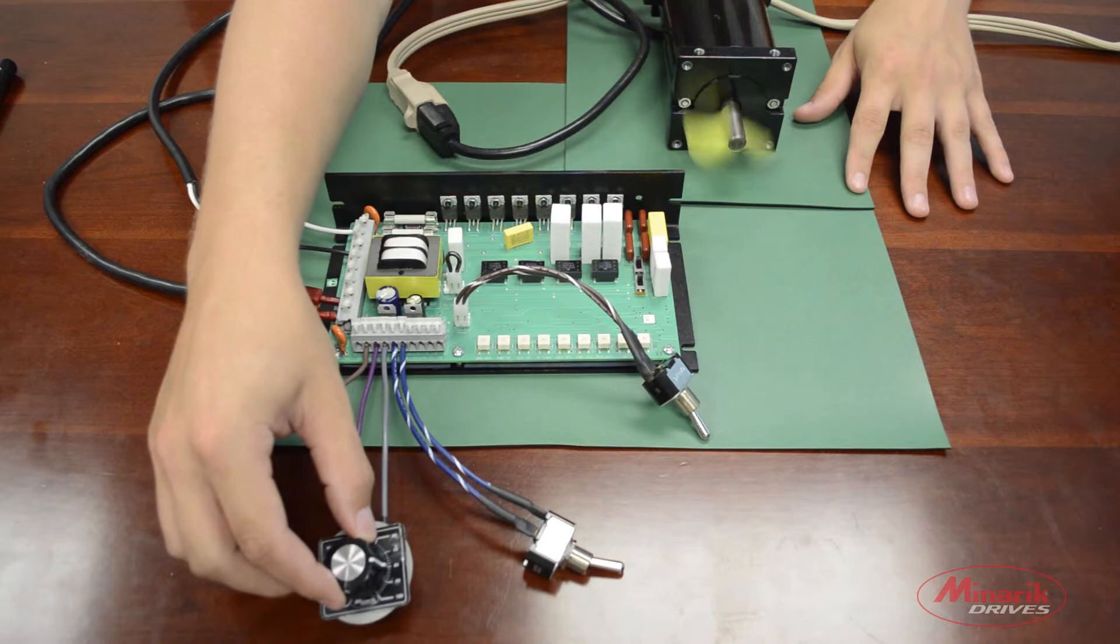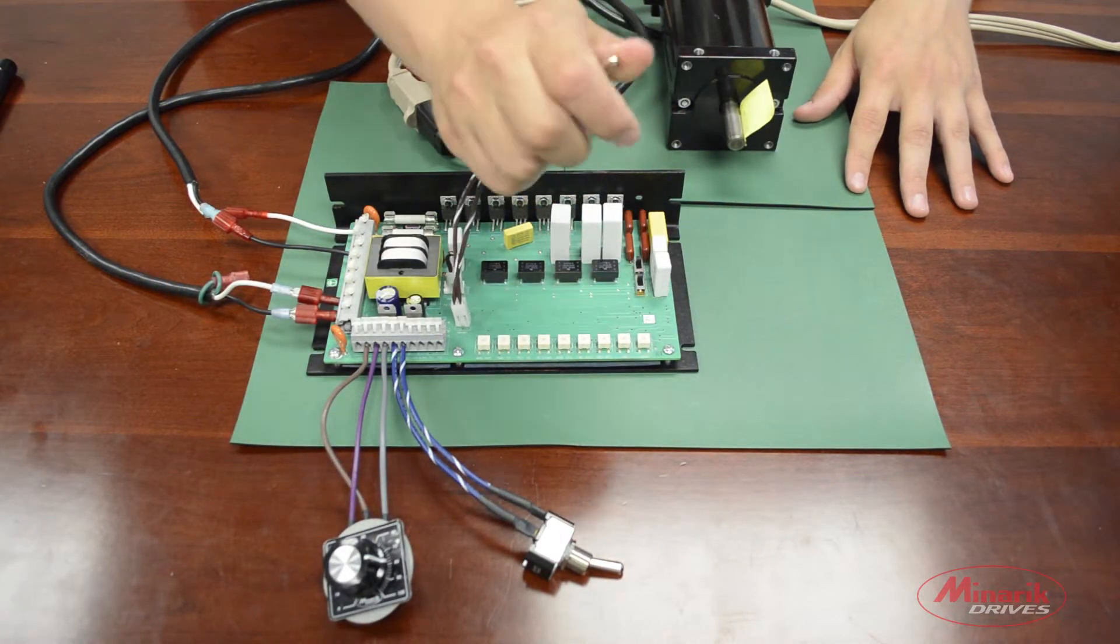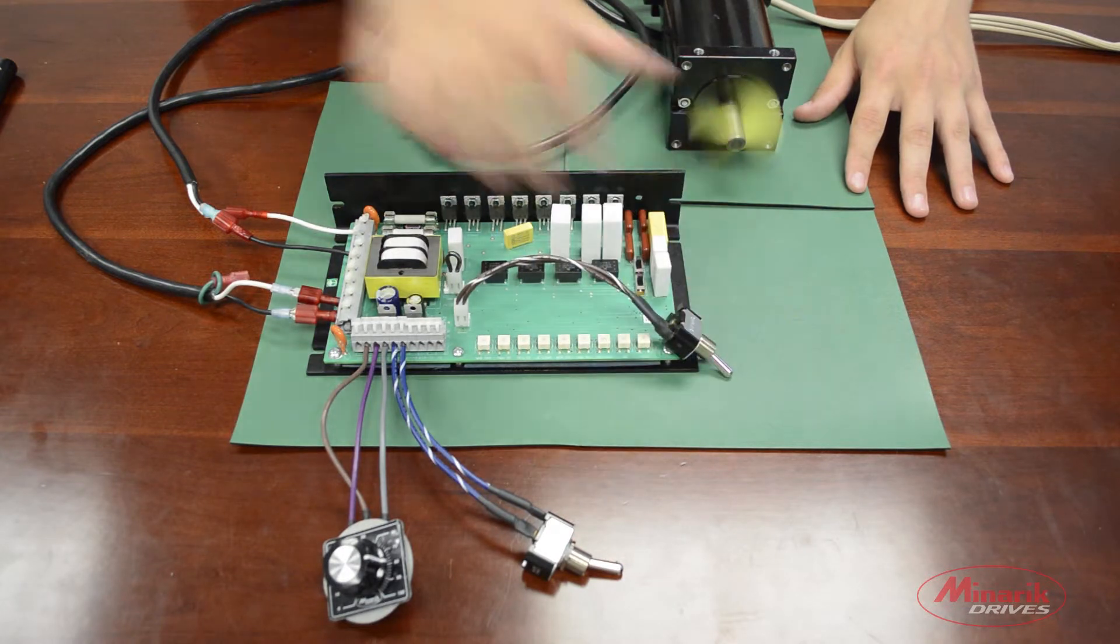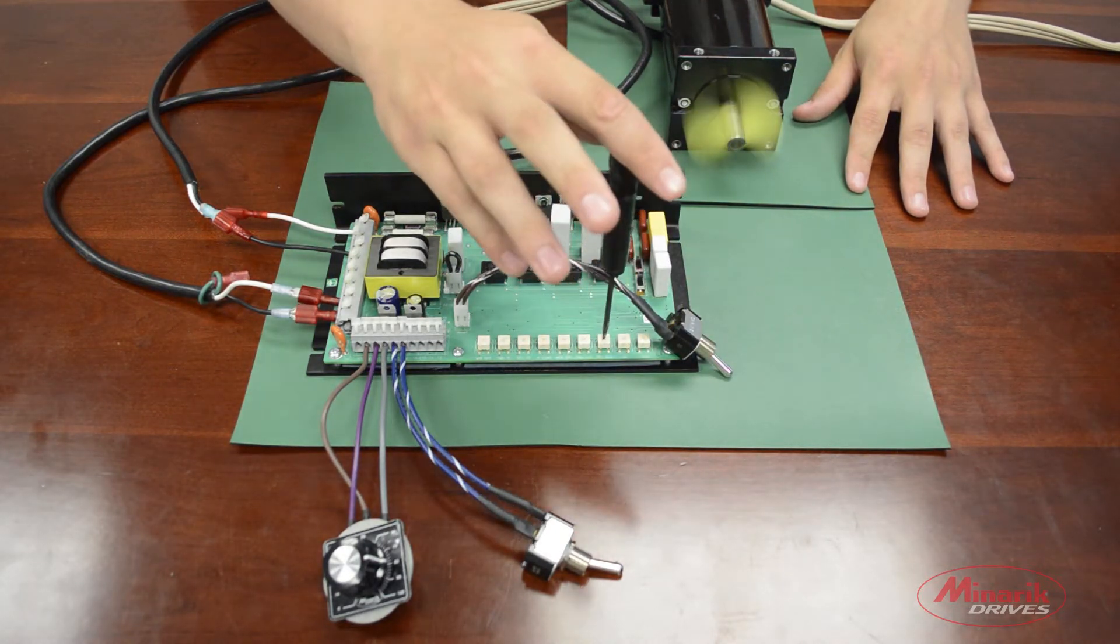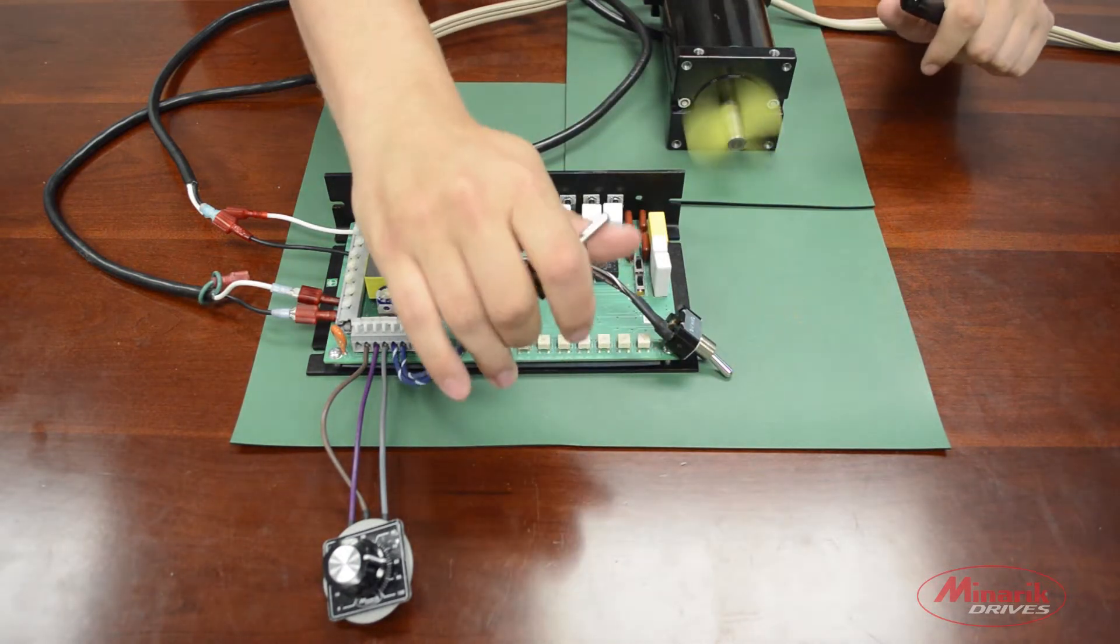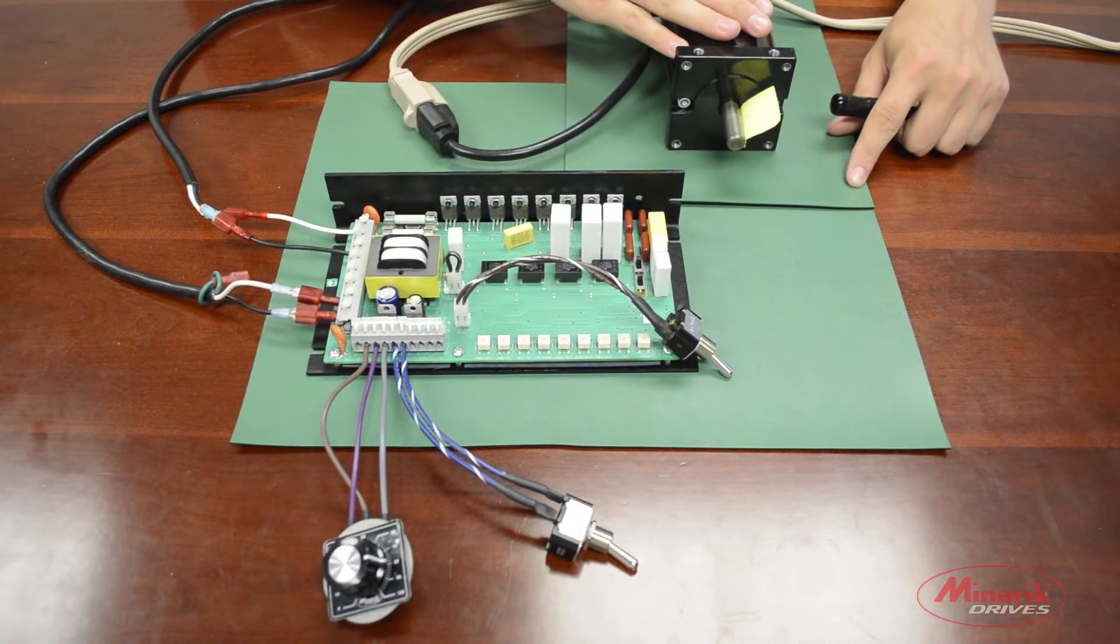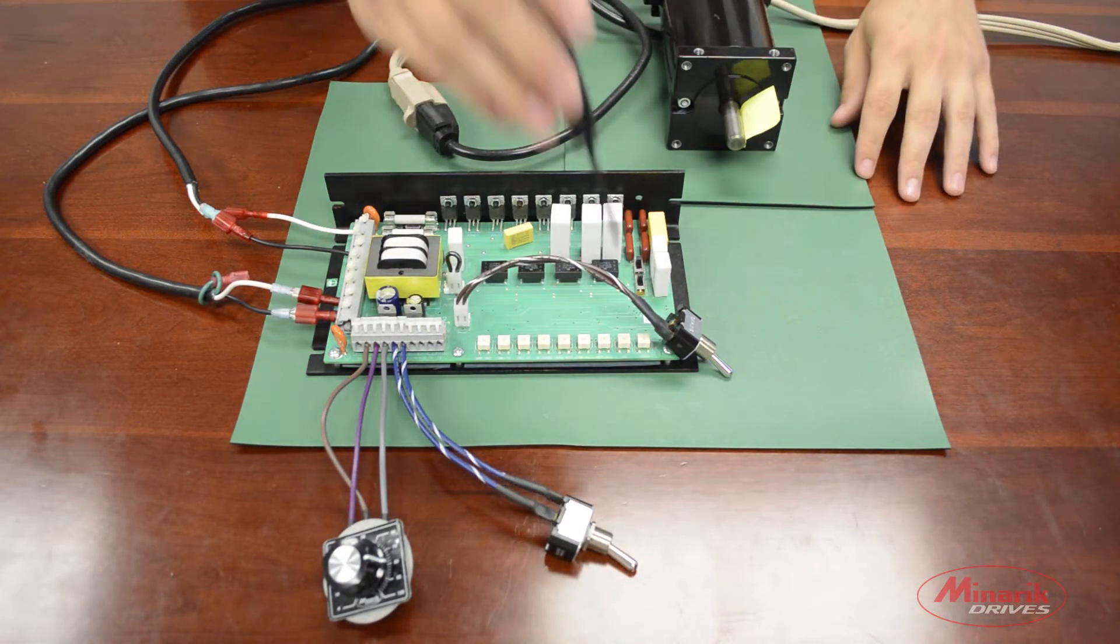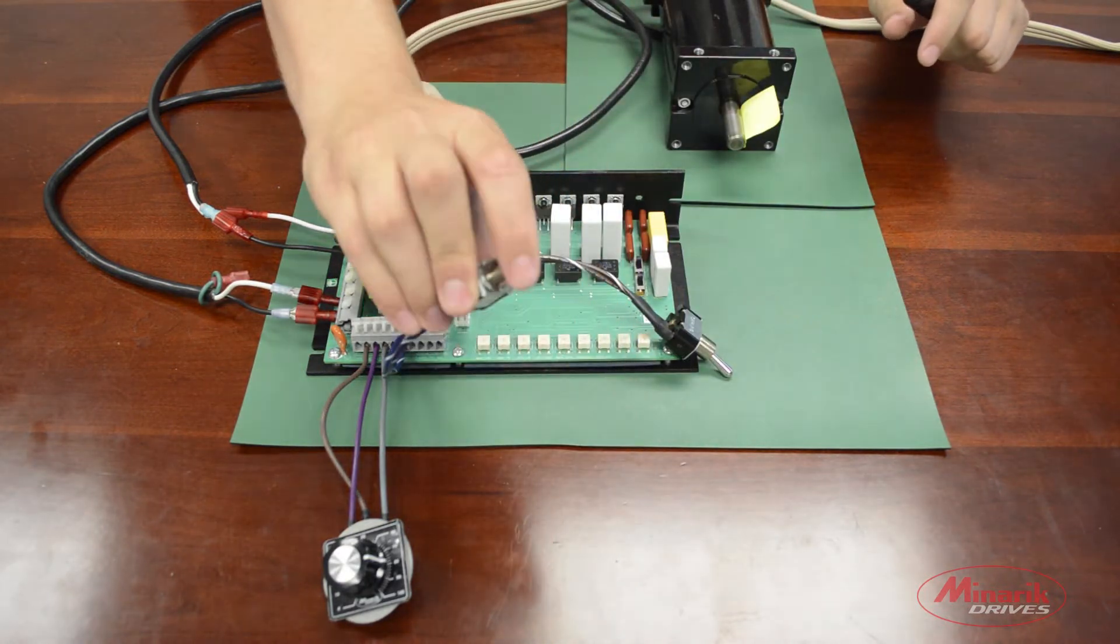The next step is to test both switches. First, the inhibit switch. And next, the run brake switch. To test the run brake switch we'll turn up the reverse acceleration trim pot. So that when we activate the run brake, we notice the motor decelerates down to zero. We'll turn the trim pot back down to zero and unactivate the run brake.